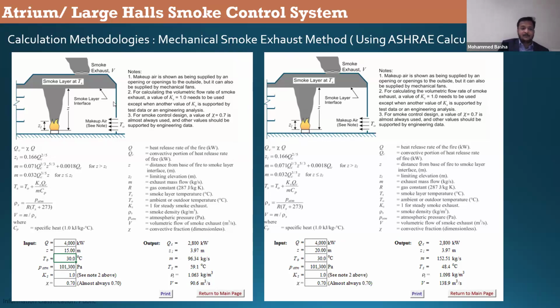You must be wondering, how come the smoke layer temperature is 60 degrees Celsius here? It should be more, right? Generally the fire generates 500 degrees Celsius, 400 degrees Celsius. Then how come the smoke will be 59? Because this calculation accounts for the atmosphere temperature as well and the height of the smoke layer interface. So the smoke layer temperature will be merely 59 degrees because of the Z height you are specifying. You said you need to maintain 15 meter clear height. When the smoke goes up, it loses its energy as convective heat transfer. That's why the temperature of the smoke is less, so do not worry that the temperature shown is very low.